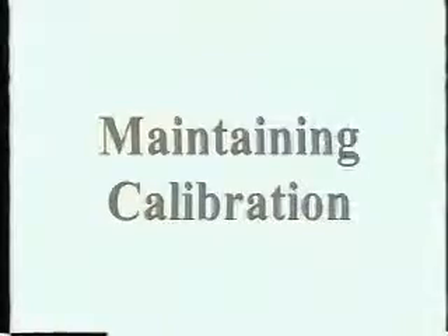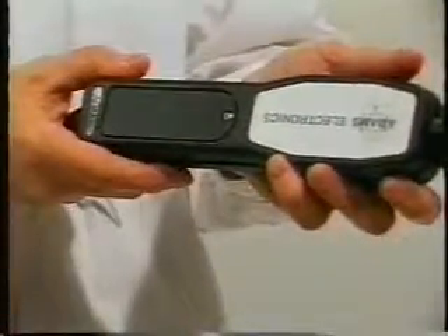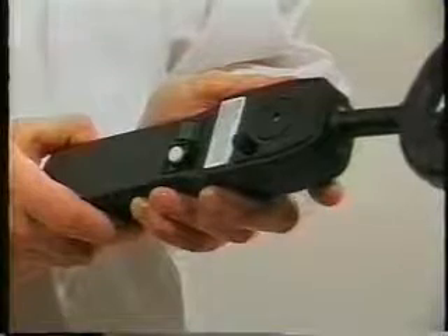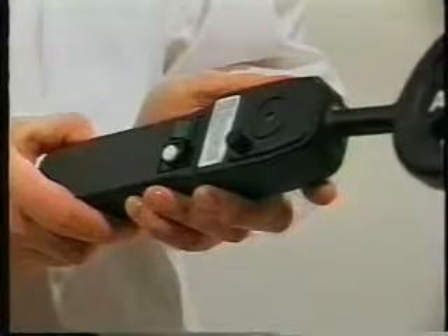Maintaining calibration. If the sensitivity control knob has been turned beyond the normal calibration point, the detector will emit a constant alarm, much the same as if the battery were low. The operator should always first check the battery. If the detector still emits a constant alarm, it means the unit is out of calibration. To remedy this is a simple procedure.